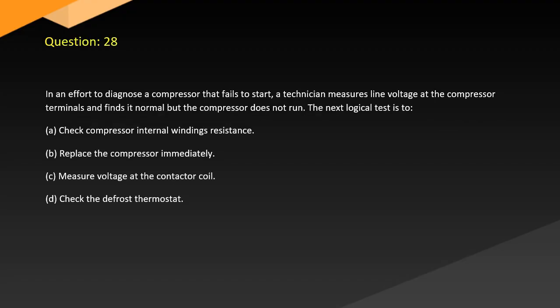Question 28. In an effort to diagnose a compressor that fails to start, a technician measures line voltage at the compressor terminals and finds it normal, but the compressor does not run. The next logical test is to: A. Check compressor internal windings resistance. B. Replace the compressor immediately. C. Measure voltage at the contactor coil. D. Check the defrost thermostat.